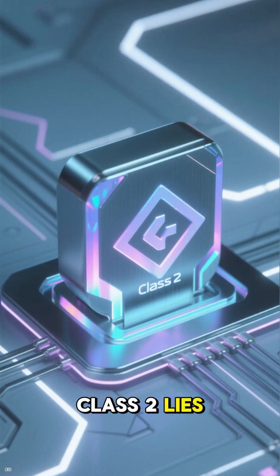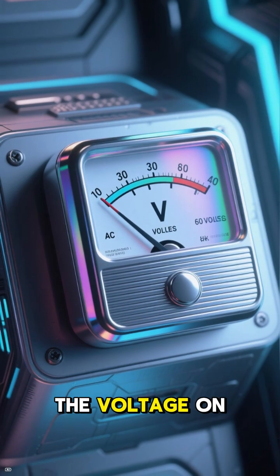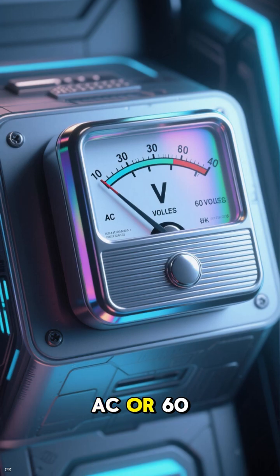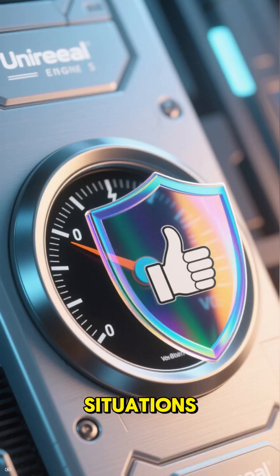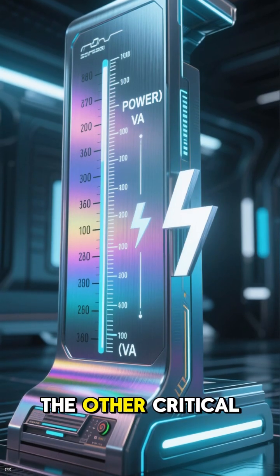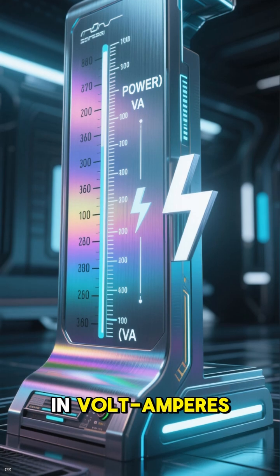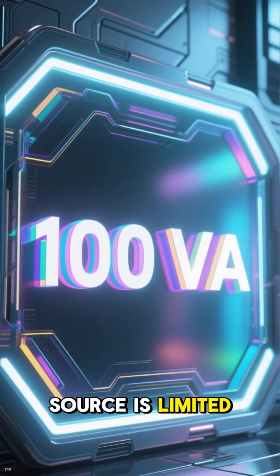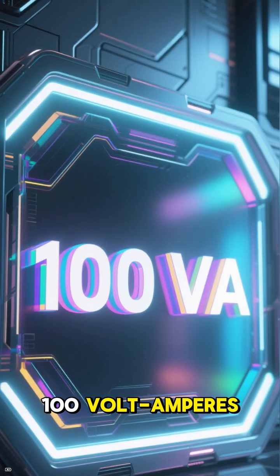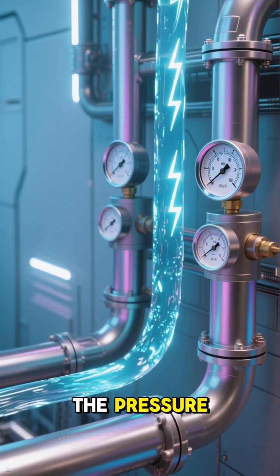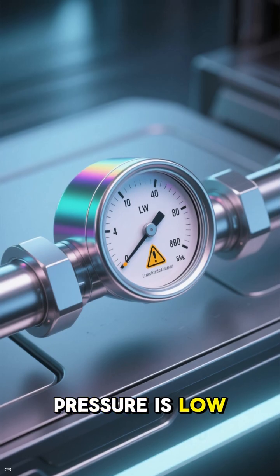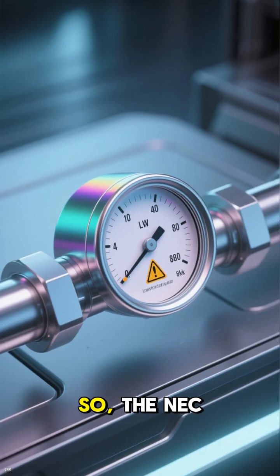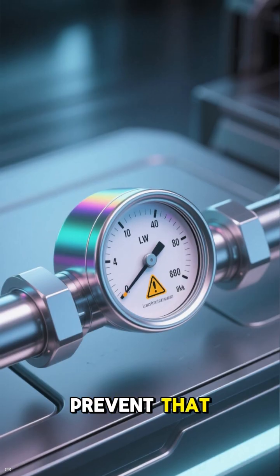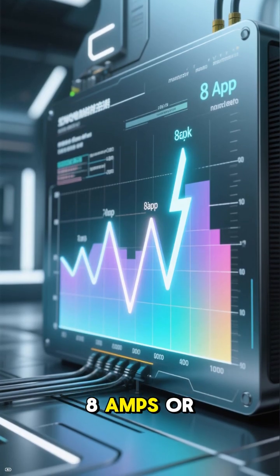The magic of Class 2 lies in its low energy levels. Typically, the voltage on a Class 2 circuit will not exceed 30 volts AC or 60 volts DC. This is a level that's considered safe from a shock hazard perspective for most situations. But voltage is only half the story. The other critical component is power, which is measured in volt-amperes, or VA. A Class 2 power source is limited to a maximum output of 100 volt-amperes. Think of it like a pipeline. The voltage is the pressure, and the current is the flow rate. Even if the pressure is low, a huge flow could still cause problems. So, the NEC limits the total power to prevent that. In terms of current, you'll often see a cap around 8 amps or less, but this is tied directly to the voltage and the 100 VA limit.